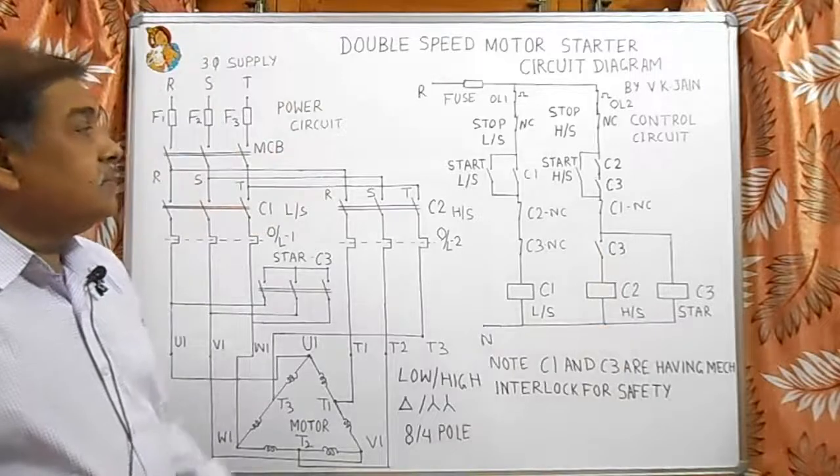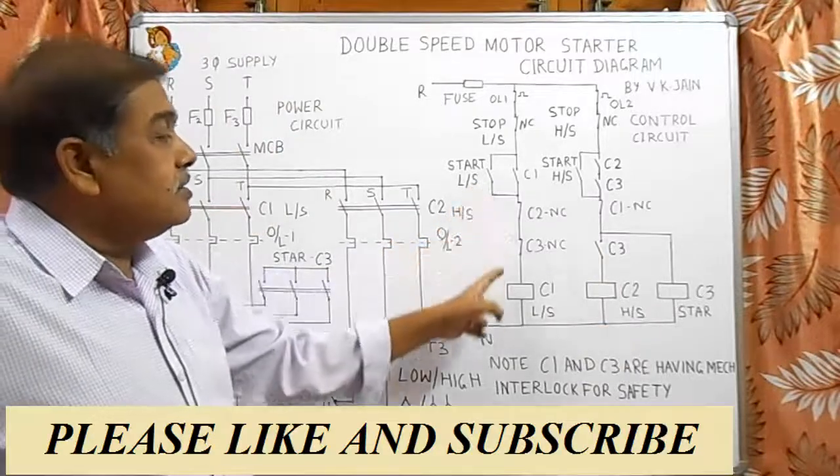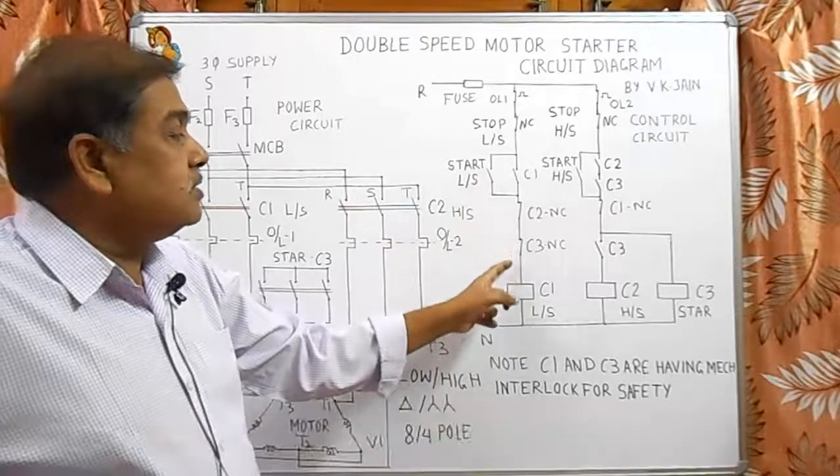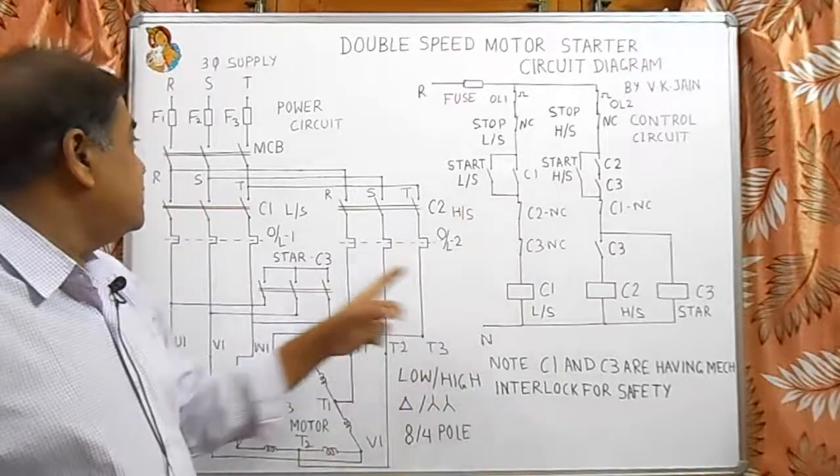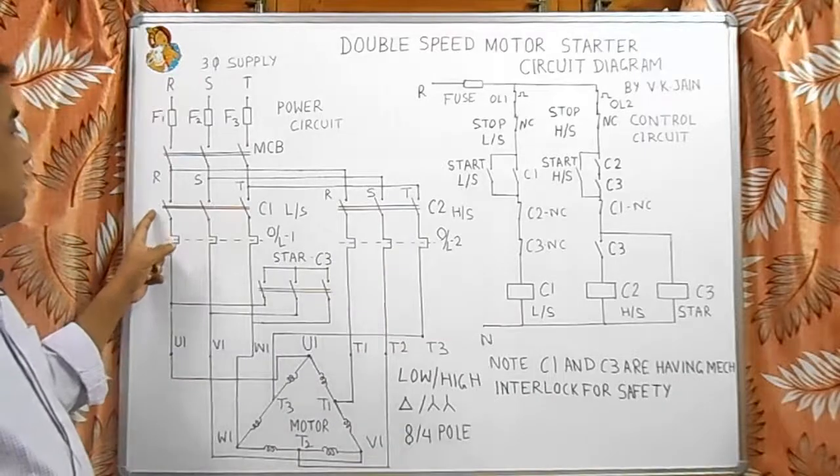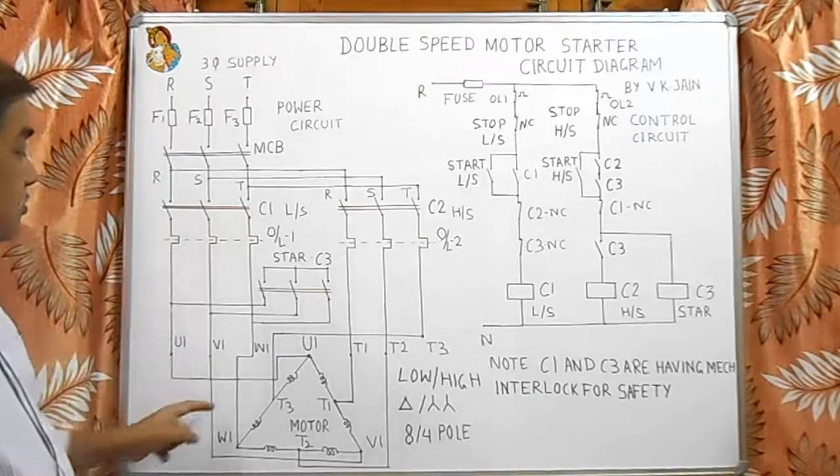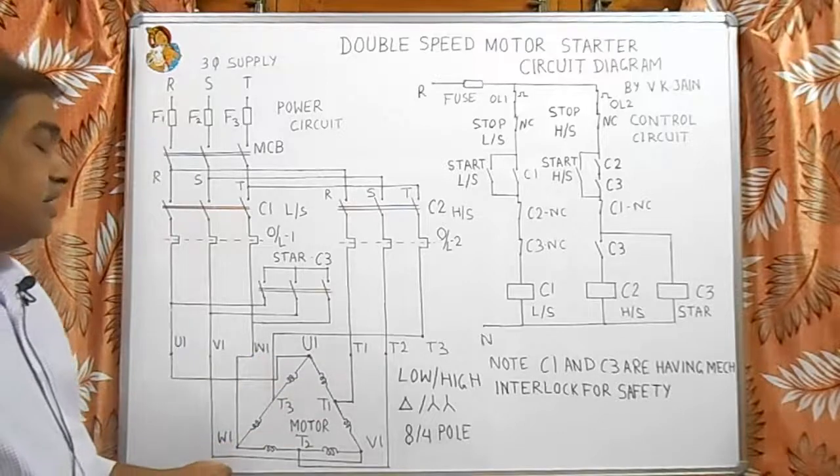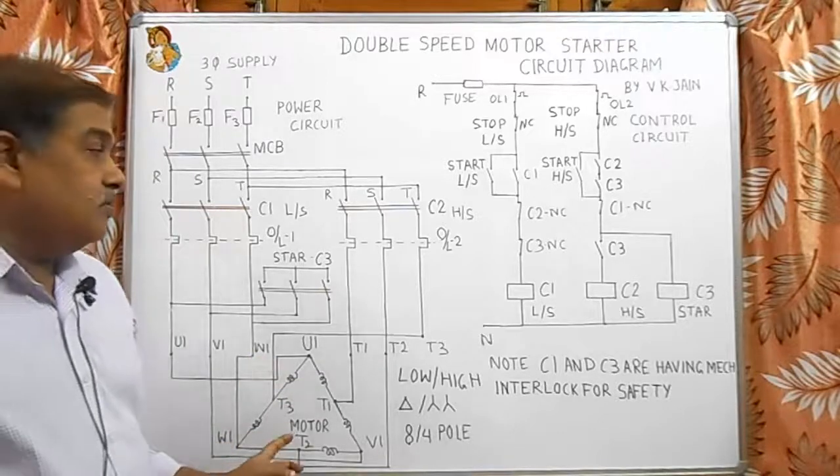When we push this button, the C1 contactor picks up and this C2 and C3 gives interlocking. As C1 contactor picks up, here C1 power contactor closes and the supply goes to the motor U1, V1 and W1 and the motor starts running at low speed.